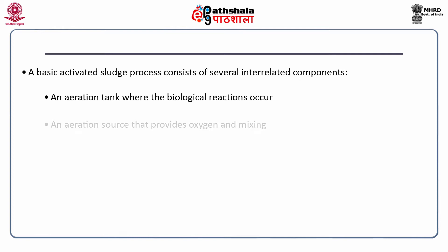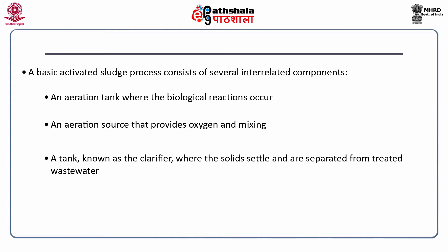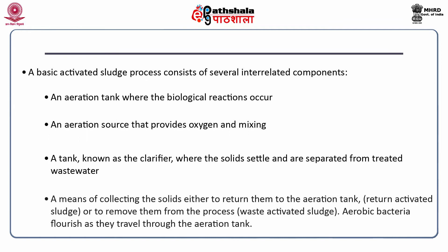The second component is an aeration source that provides oxygen and mixing of the wastewater. The third is a clarifier tank where the solids settle and are separated from the treated wastewater. The fourth is a means of collecting the solids either to return them back to the aeration tank to maintain the microbial population or to remove them from the process. The sludge that is removed from the process is called waste activated sludge.